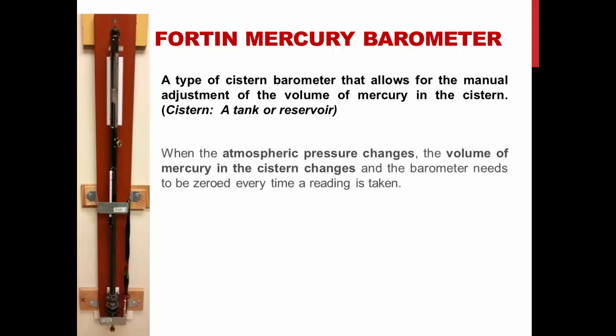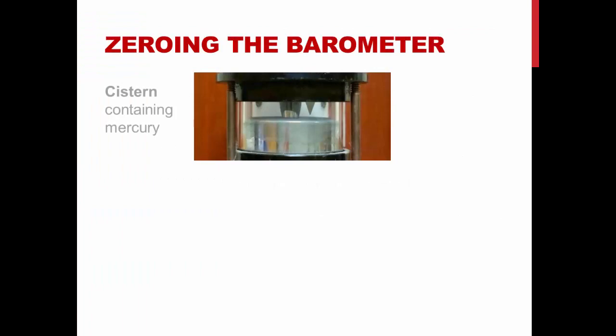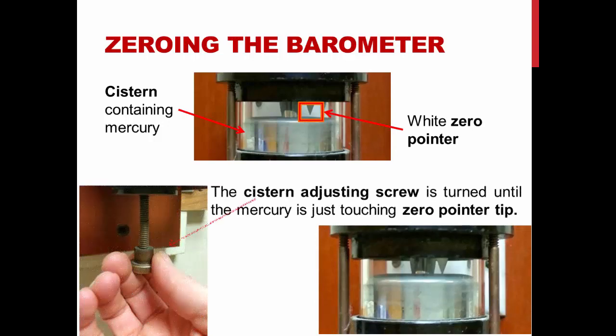When the atmospheric pressure changes, the volume of mercury in the cistern changes and the barometer needs to be zeroed every time a reading is taken. In the top picture of this slide, you can see the cistern containing mercury and the white zero-pointer. The bottom picture depicts the cistern adjusting screw being turned until the mercury is just touching the zero-pointer tip.